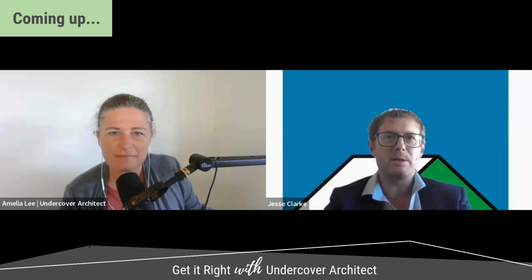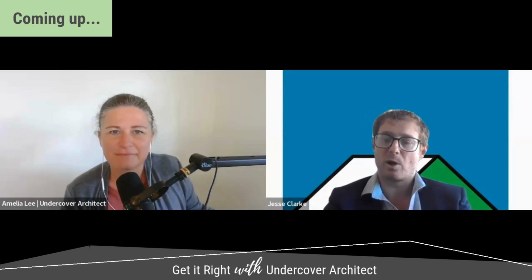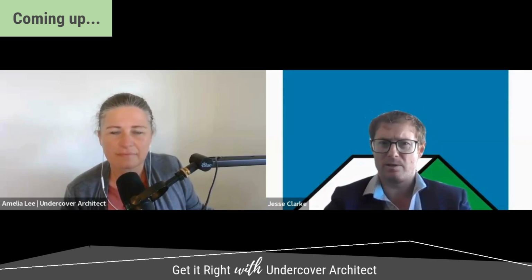They may not be condensation. It may just be damp building materials, because when building materials get cold, they start to absorb more moisture into the pores. So you've got these damp building materials creating higher humidity surrounding that building material. When you get high humidity above 70, 80% for a prolonged period of time, then you potentially induce mold growth.